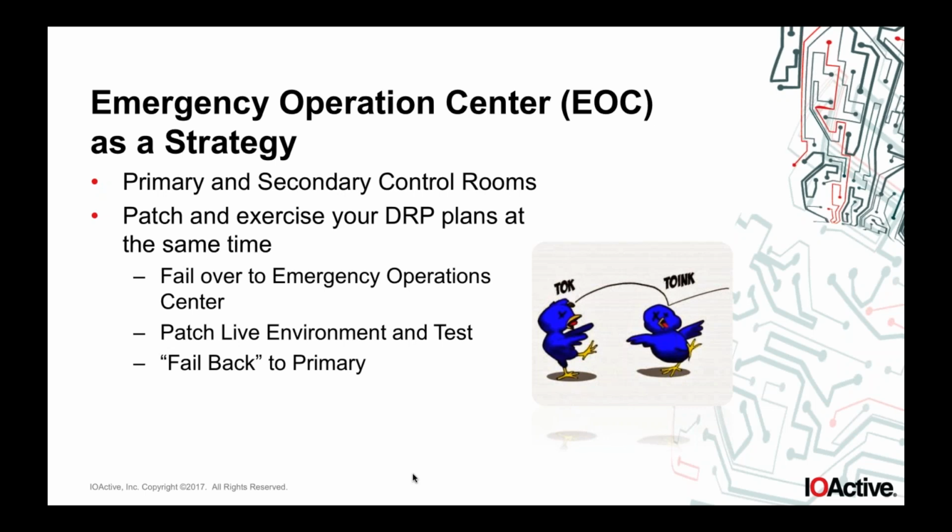But when we started to look at the physicality, the location of some of these services, we found that almost all of them were in tsunami flood zones. So yep. With that being the case, it's like, well, guys, that's great, but you didn't really solve the major problem that you're trying to engineer around. Yep. And in many cases, that's something catastrophic, like a tsunami.